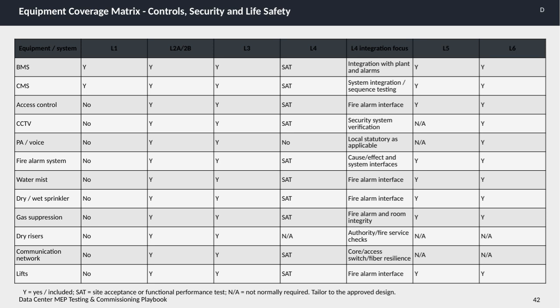Integration points are critical here. For example, integrating the BMS with plant operations and alarm systems, or verifying security system through CCTV checks. Access control systems interface closely with fire alarms to maintain building safety protocols. Similarly, fire suppression systems, including water mist, sprinklers, and gas suppression, all require testing focused on their interaction with fire alarm systems and room integrity. Some systems like dry risers and communication networks have specific notes. Dry risers need authority and fire service checks, while communication networks focus on switch and fiber resilience.